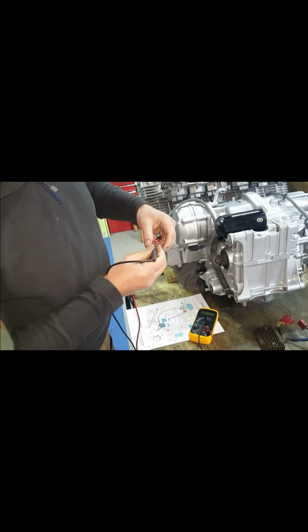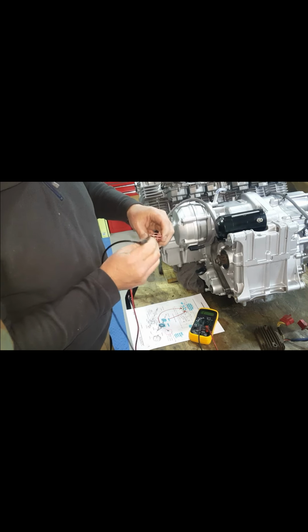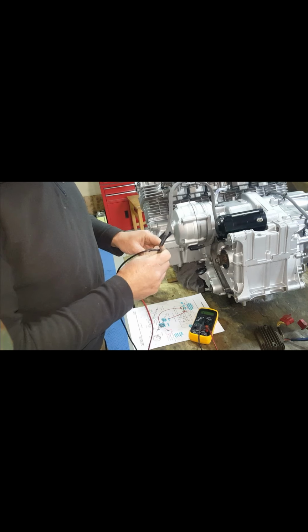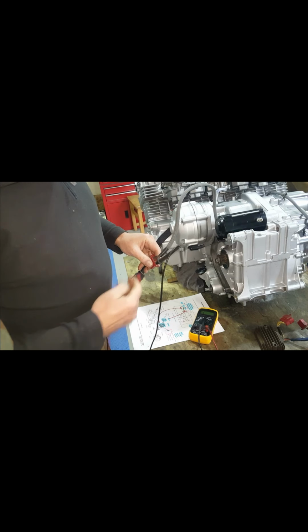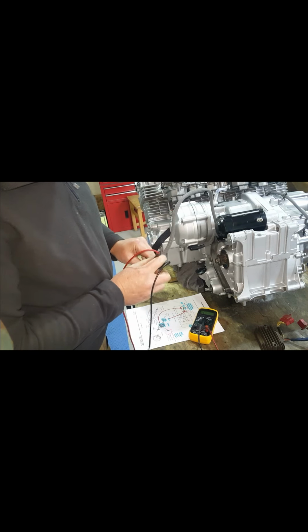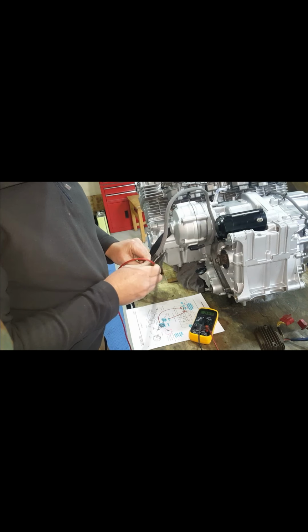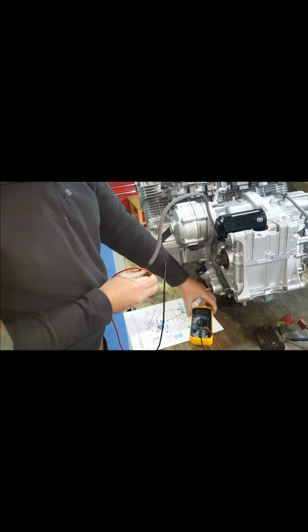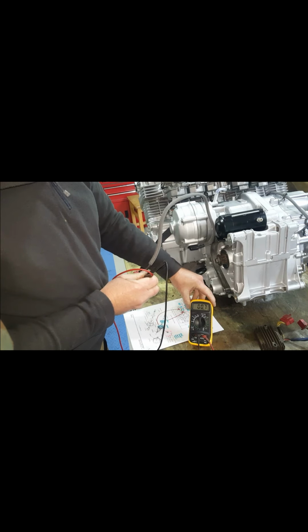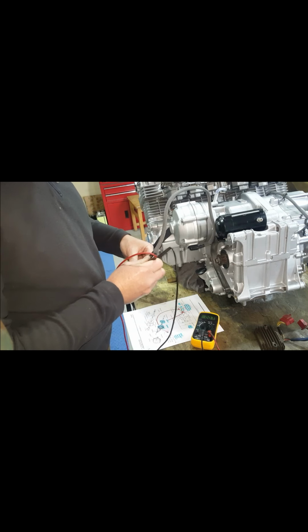Now what we're going to do is just put our meter in here - in fact, I'm probably going to go in the back, it's probably easier. And we can see we've got about 0.8 of an ohm there, 0.7 of an ohm. So we then need to take the 0.2 off that, so we're around about 0.5.